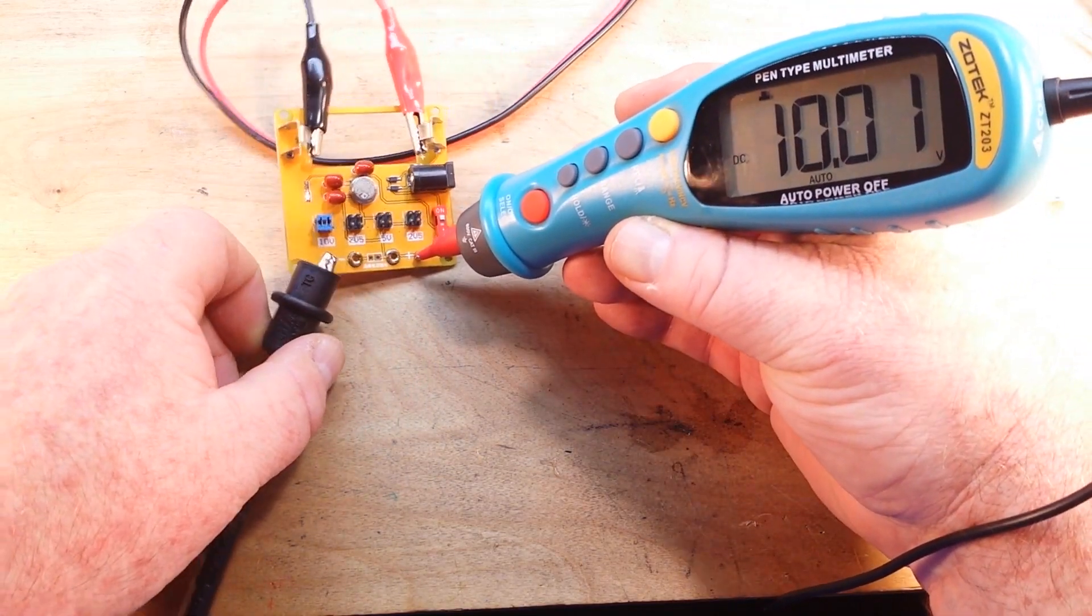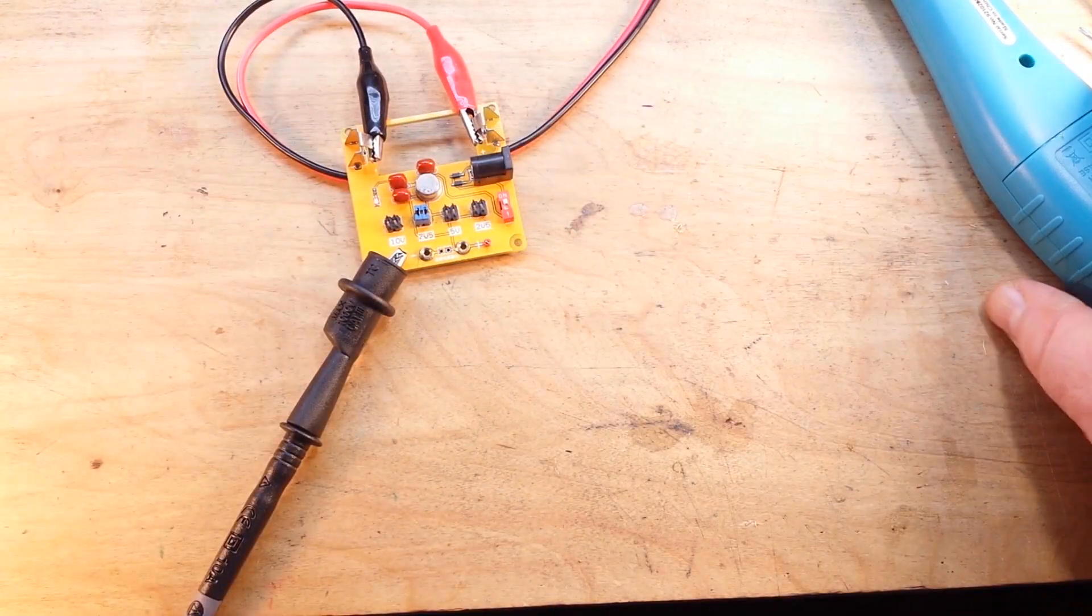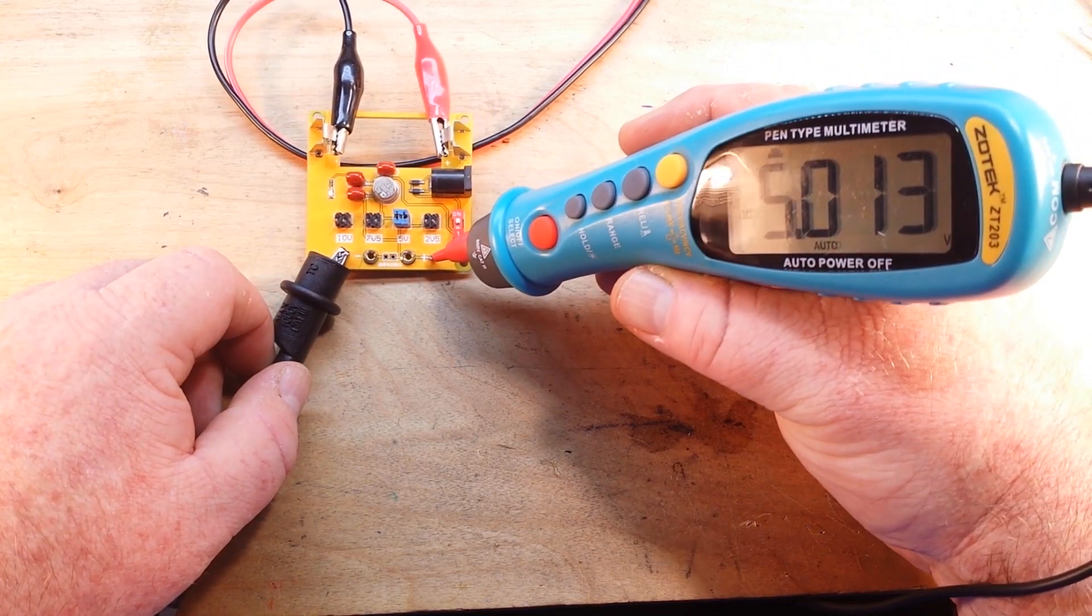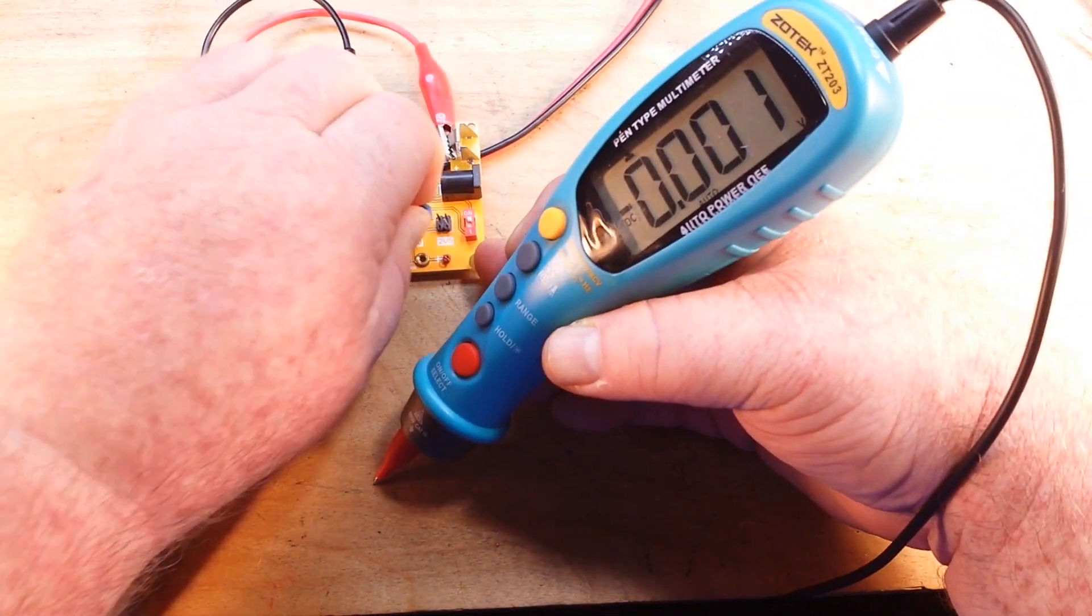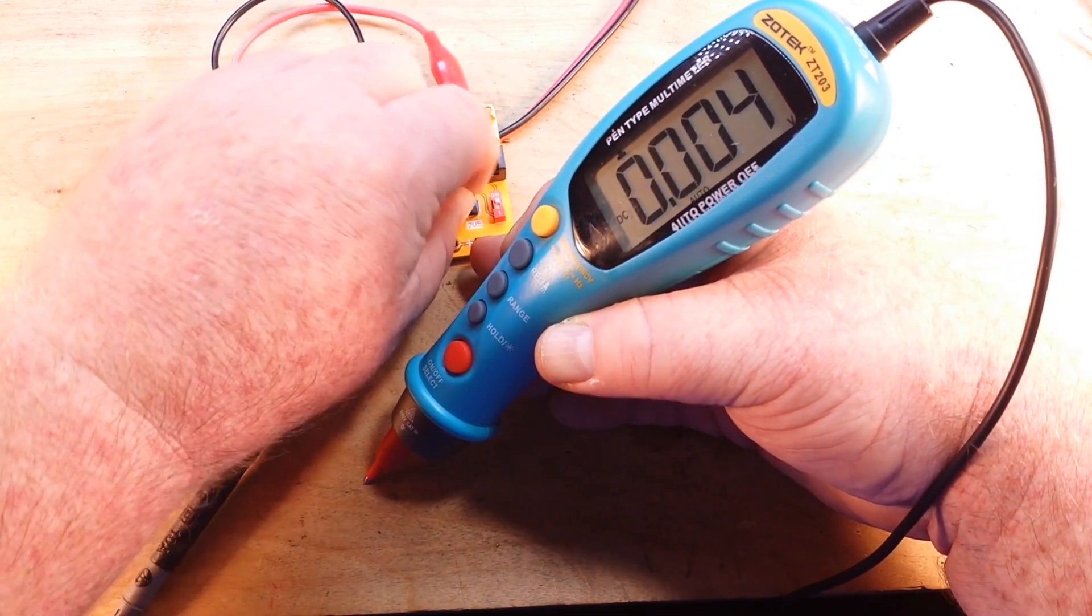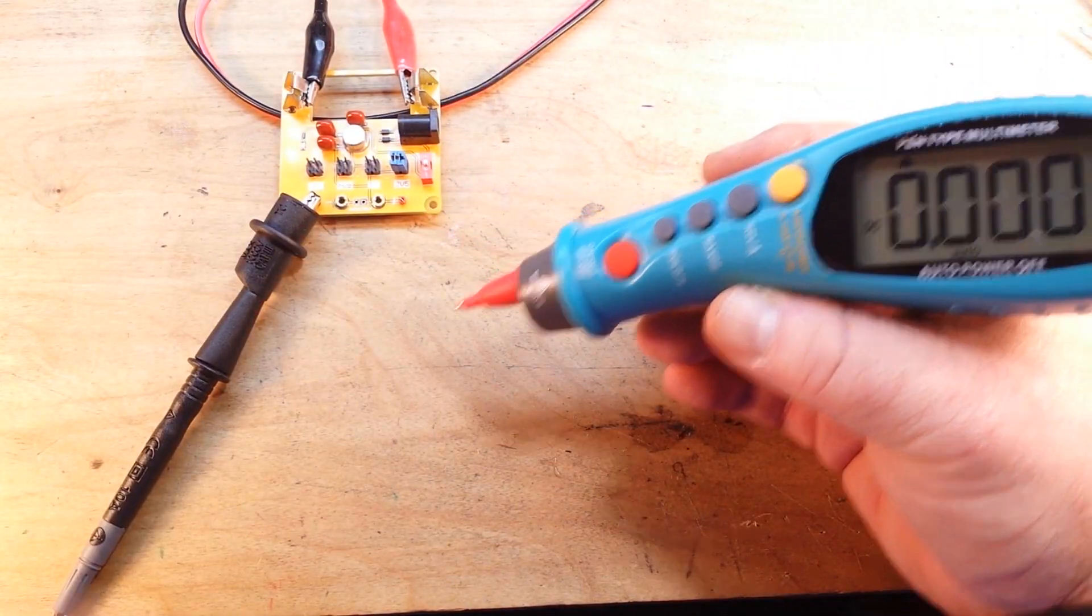All right, so let's see what we got here. 10 volts, 10.01, very nice. Fell right out of my hand. Moving on down to 7.5 volts. Right on. Moving down again, five volts. 5.013. And finally, two and a half volts. Man, I have trouble with these little jumpers. 2.5. Hold on. You know what? I think I got something for that.